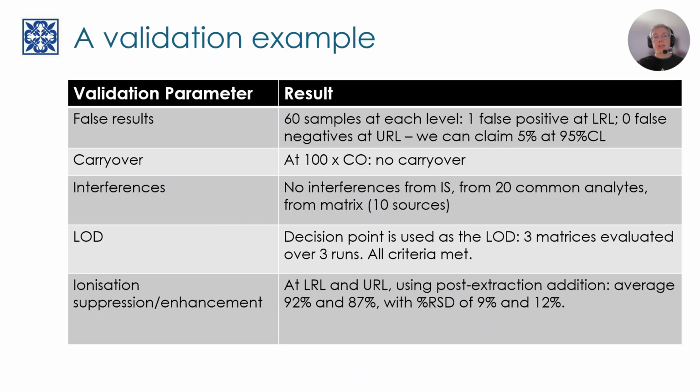If we had significant suppression or enhancement at either concentration, this would jeopardize our false results proportion that we evaluated above, but we did a good job in the development of this method because it seems mostly free from ionization issues, with good averages, good percent RSD.